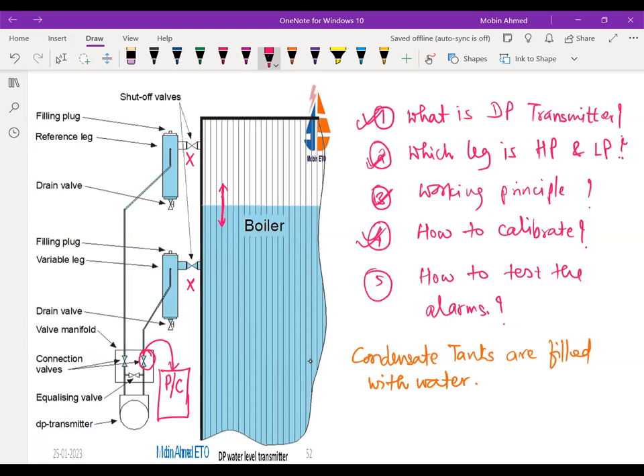So once it is, you can note also what is the pressure. It is going to give the high level alarm, and at what pressure, it is going to give the high level trip. And same way, if it is going to be the low level alarm and low trip. So once you do it, you can record. One is the actual procedure, that is how you are going to do it.